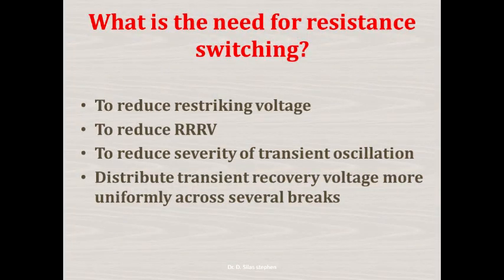What is the need for resistance switching? To reduce re-striking voltage. To reduce RRRV. To reduce the severity of transient oscillation. To distribute transient recovery voltage more uniformly across several breaks.